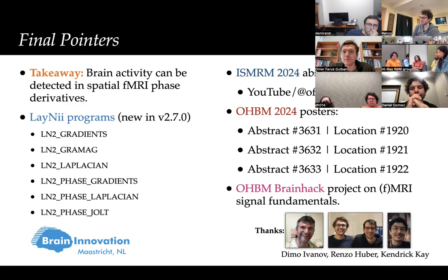you are two orders of magnitude more sensitive to BOLD effects than they are, meaning also that your signal stability is going to be much less than what they have. I think they had a 0.1 degree phase stability. I don't think you can ever get that in your BOLD type of data. So I think you shouldn't be looking for Laplacian phase effects in BOLD data to try to find conductivity changes related to fMRI.